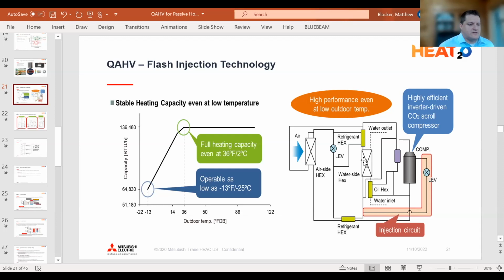get your defrost done. So because of the temperatures and pressures that the CO2 runs at, the defrost is much quicker than even a VRF system. It's probably in the range of 5 to 7 minutes, in kind of a worst case defrost scenario. But really, if you look at it, you're using the electric of the compressor for your defrost, as well as the heat rejection, that kind of thing.